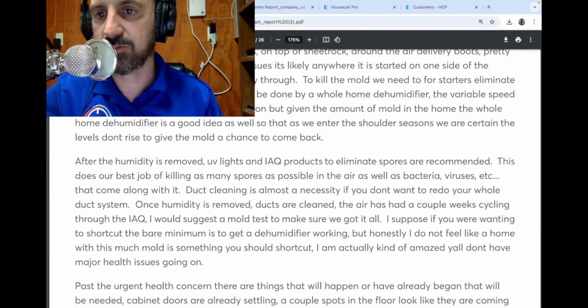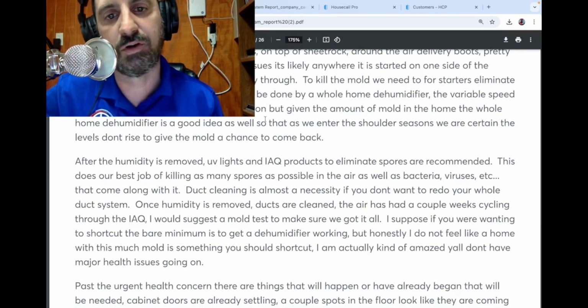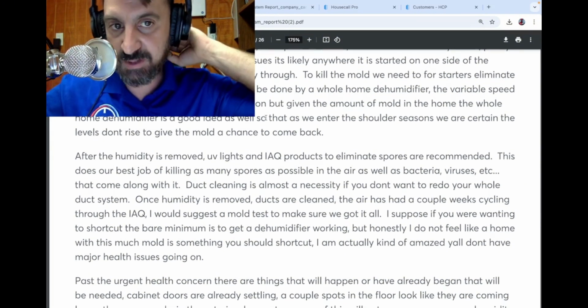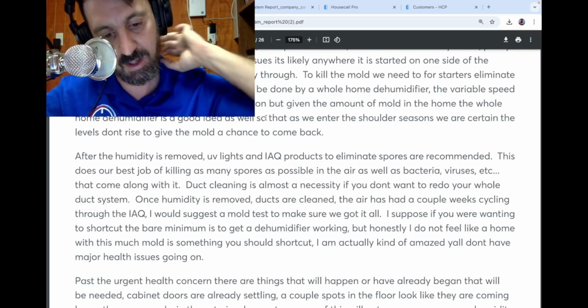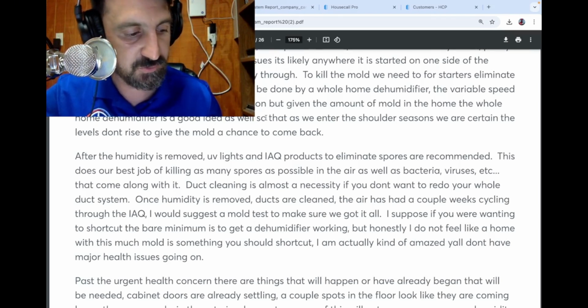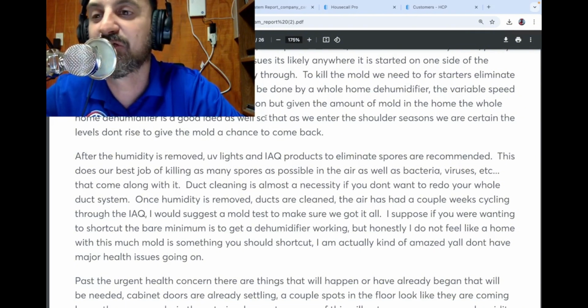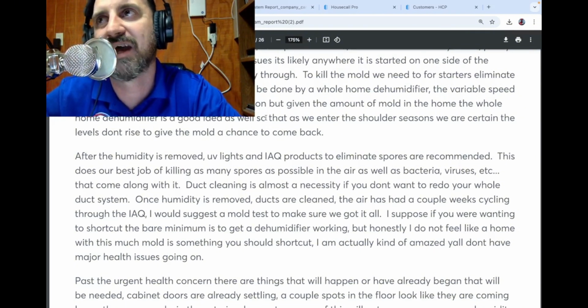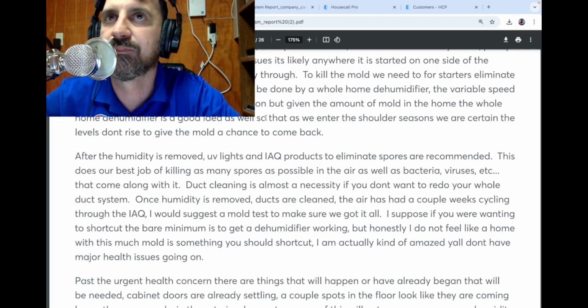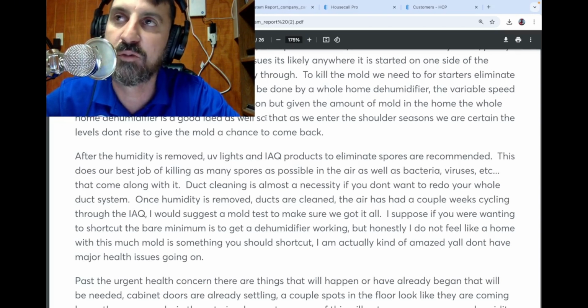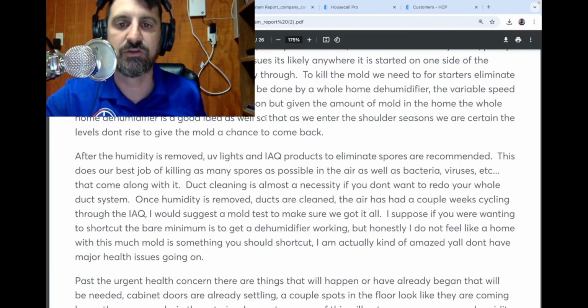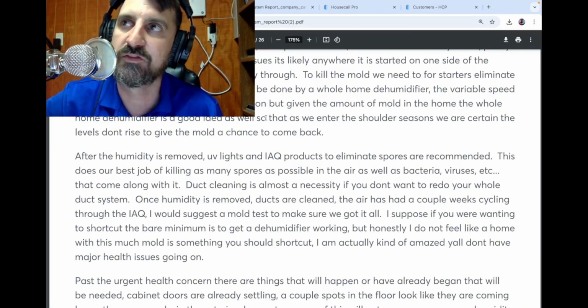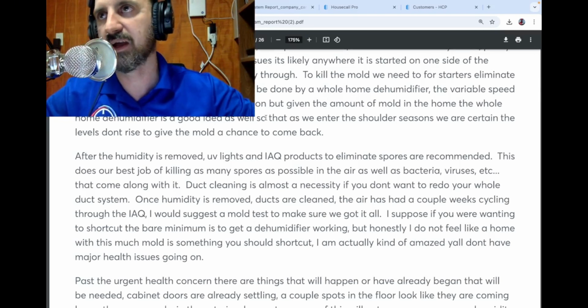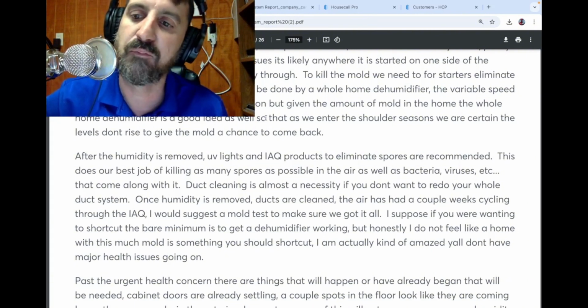So basically, for starters, we need to eliminate the humidity, stop the growth. It can be done by a whole home dehumidifier. It leaves that oversized AC short cycling out there, and it'll short cycle even more once the humidity is under control because it doesn't have to work as hard. But basically the whole home dehumidifier would drop the humidity levels. I'm proposing to do it with its own duct system so that we can have a sensor in the attic and one in the home, and we can circulate air through it and dehumidify both that way.